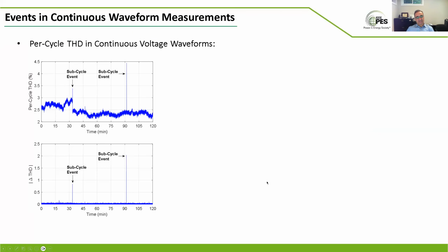Here's a completely different example. We had a slow and a fast. Let's go back to the slow waveforms. This is closer to basically a renewable facility. A power quality meter is tracking total harmonic distortion over time. See, the time is in minutes. This is a lot of time. This is not a waveform.